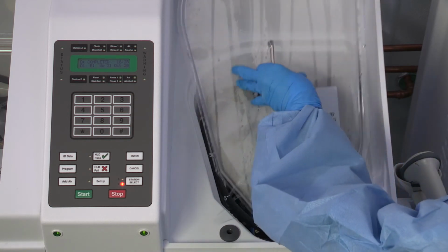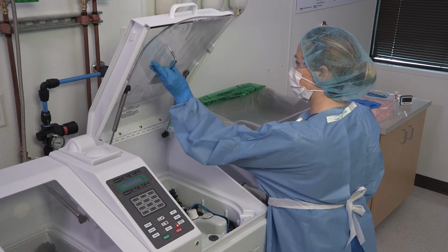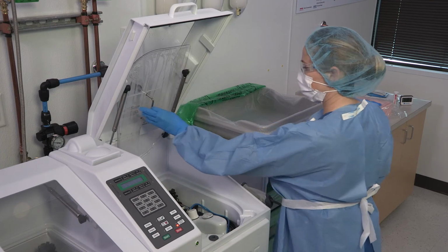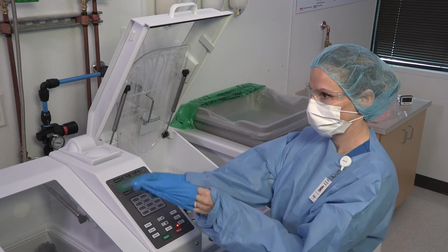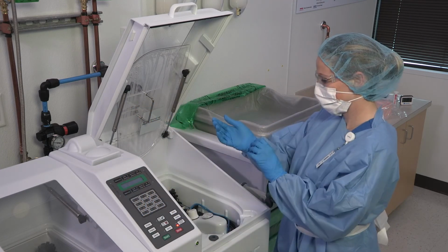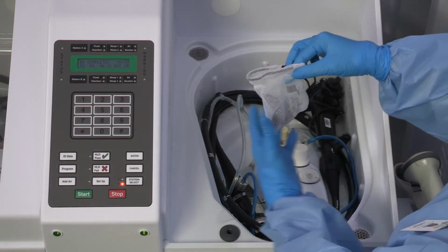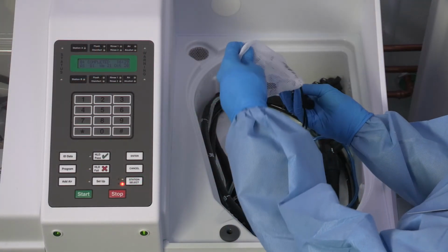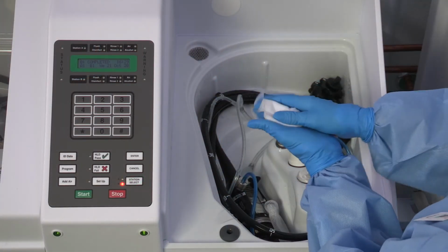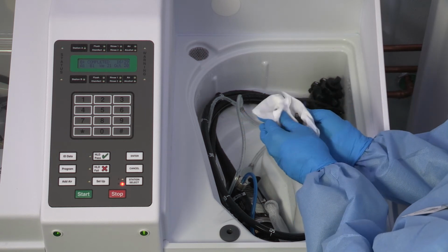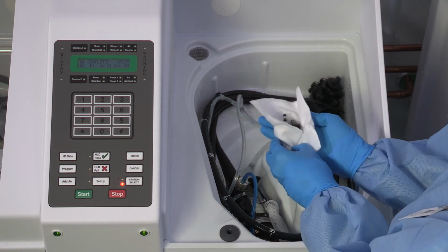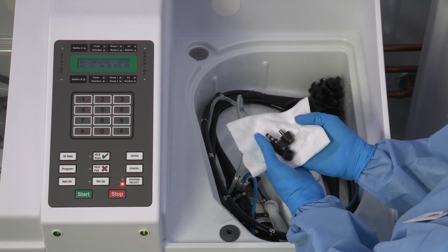If no fluid, remove the floating lid and store it behind the lid supports so it does not rest on the hinges. If the cycle completed successfully, don clean gloves and remove the accessory bag. Dry contents with a clean, unused, lint-free cloth and store the reusable parts with the endoscope as a set.